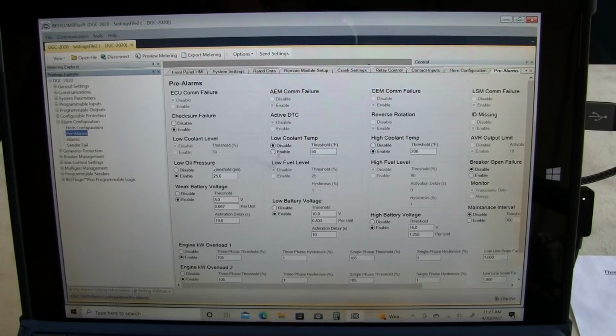Pre-alarms for the gen set, or for the engine, really. Let's see. Low oil pressure. We have that pre-alarm set at 25 pounds. Weak battery voltage is enabled at 8 volts after a 10-second delay. So if, for example, the unit is cranking and while cranking that battery voltage drops to 8 volts for 10 seconds, it'll trip a weak battery. Low battery voltage is set at 10 volts. Activate after 10 seconds. Low coolant temp is disabled. I could enable that. We'll go into why that's not enabled in a minute.